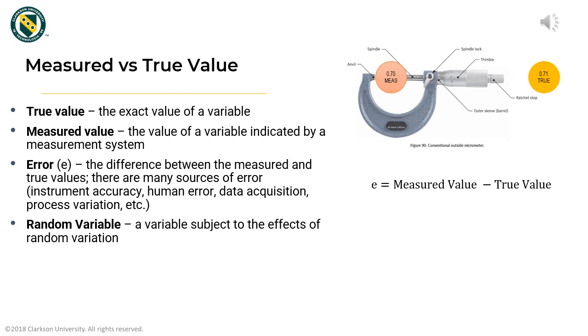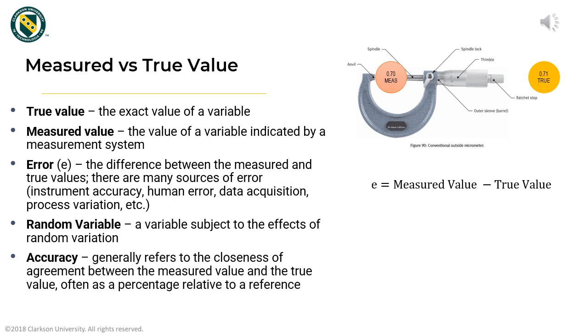Often, an estimate for the value of error is based on a reference value, such as the reference standard during an instrument's calibration, or the range or maximum value. This percent accuracy, also known as relative accuracy or just relative error, is helpful for evaluating a measurement. Notice the absolute value of error is often used, as the magnitude of errors is the primary concern.